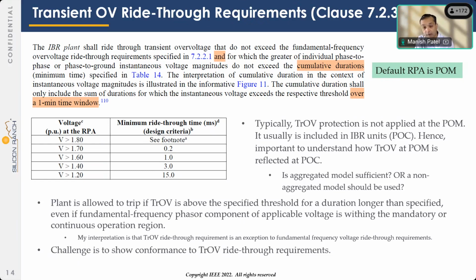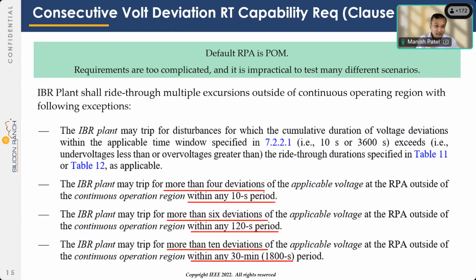We need IBRs to ride through transient voltage, but how to write a requirement, how to test it, how to show conformance remains a challenge, right? All right. The last one here, consecutive voltage deviation ride-through capability. This is clause 7.2.2.4. This is the second nightmare of my life. Again, I was in charge.